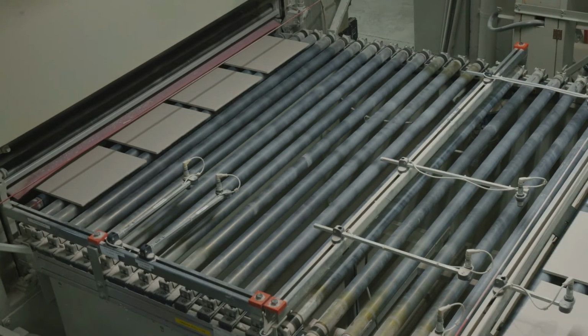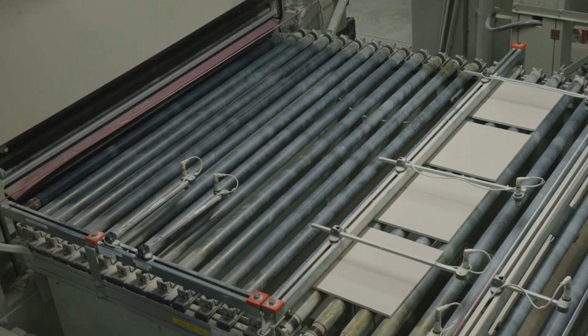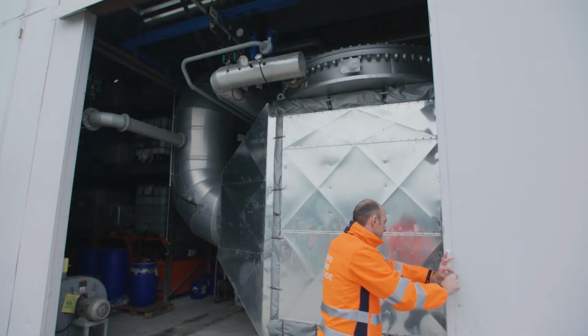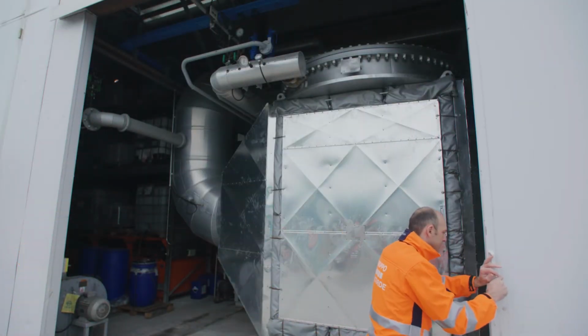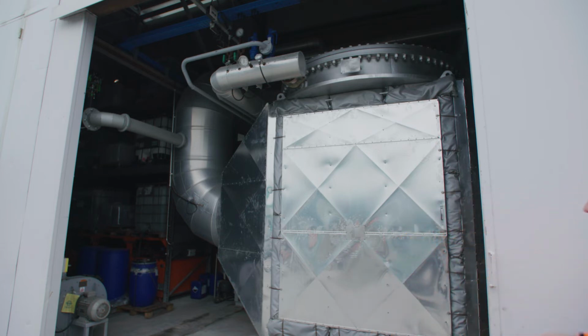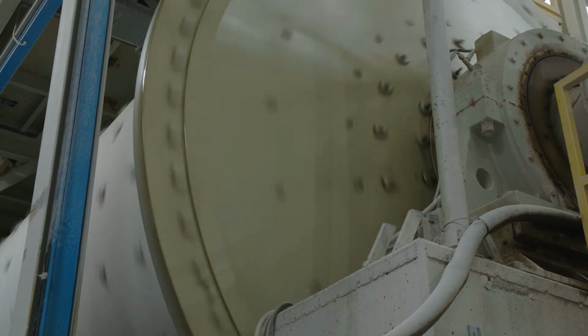To test the concept of recycling waste heat in the ceramics industry, a third heat pipe heat exchanger was installed at the production facilities of Atlas Concorde near Modena, Italy. For the engineers, it was important that the unit would not interfere with the actual production process, keeping all piping and heat transfer processes outside the plant.